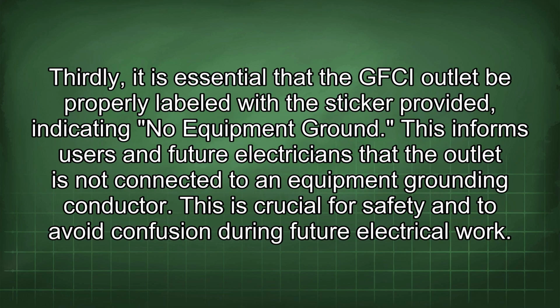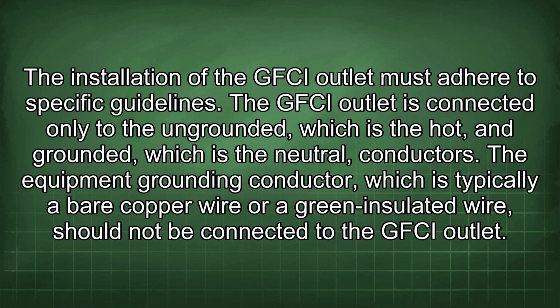Thirdly, it is essential that the GFCI outlet be properly labeled with the sticker provided, indicating "No Equipment Ground." This informs users and future electricians that the outlet is not connected to an equipment grounding conductor. This is crucial for safety and to avoid confusion during future electrical work. The installation of the GFCI outlet must adhere to specific guidelines.